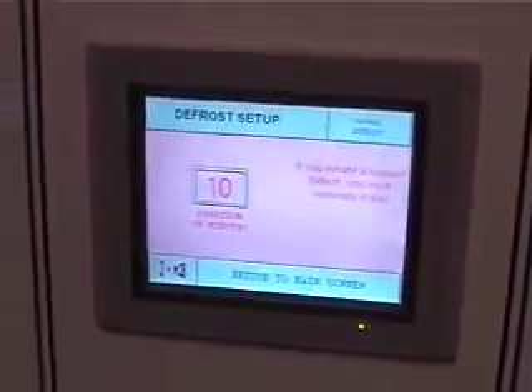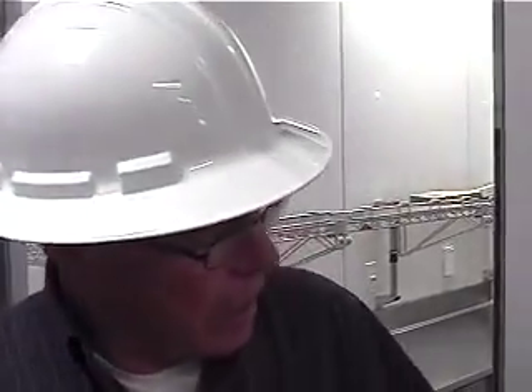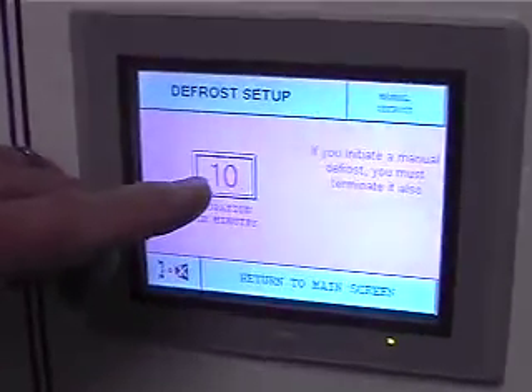Talk about defrost. In most 40-degree rooms, I mean it's almost 40 degrees Fahrenheit, you don't need to defrost, but in a room that's built to maintain such a tight temperature tolerance, it has no time to defrost, and we're running the compressor all the time. Theoretically speaking, if you're running a room at 39 degrees, your saturated suction, your coil, is 29 degrees, which is below freezing. So you're going to develop frost in there at some point if everything's working the way it's supposed to. So the controller's set up at midnight to go into defrost, and we basically give it 10 minutes, and that's sort of what we factory set.